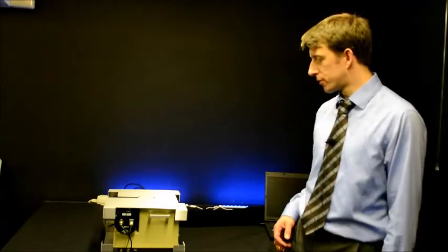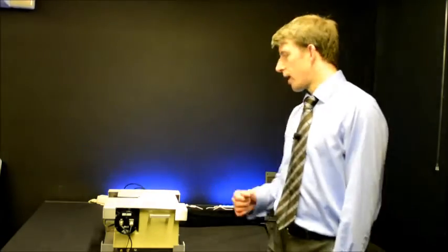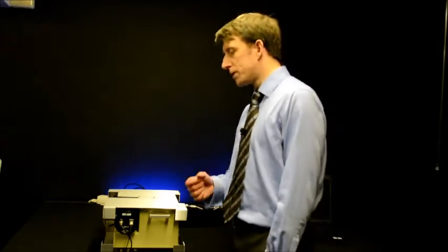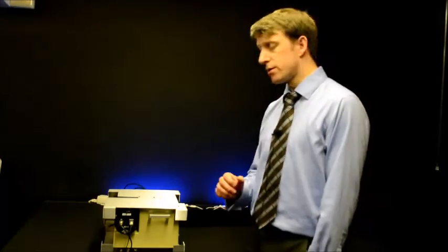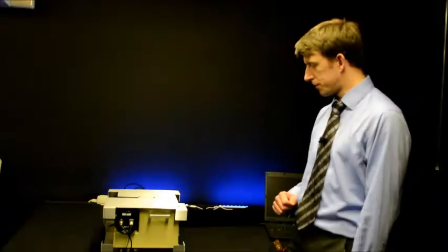Behind the entrance port is placed an order sorting filter wheel, a 6-position filter wheel which provides a shutter. It has a clear, an open position for measurements up to 400 nanometers. From 400 nanometers, the OS400 long pass filter is fitted to suppress higher diffraction orders, and at 700 nanometers, a second filter, the OS700 long pass filter, is installed.